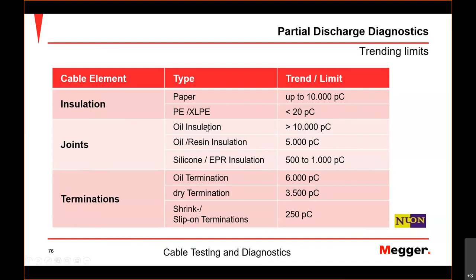But one thing, looking at all these numbers in joints, how much is acceptable or not? Well, would I accept that? Not really. You can have a joint that has less than noise level, so practically no partial discharge. A joint, when it's done properly, has no partial discharge, up to 1.7 at least. If it does, that means something is going on. So I wouldn't really accept that in any case. You might say, okay, 500 picocoulombs. If it's below 1,000 in general, I would say that's okay. If it goes above 1,000 picocoulombs, then you might say, well, we might consider that within the next year, double check, do a repeated measurement and see if it got worse or not. But in general, you're supposed to have no partial discharge.